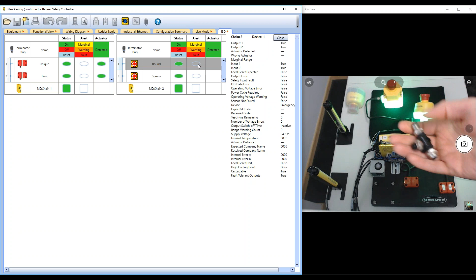What you get with ISD is it'll tell you when a door is open, so in the system you'll see the low-coded system tells you it's open. I can also, as part of preventative maintenance, have my OSSDs on, this chain is good, but I'm getting a warning, a marginal alert for this RFID switch because it's in a state where it's starting to sag. It's still closed, but you need to address it because the actuator is 14.2 millimeters away from the sensor, if you can read this on my screen.